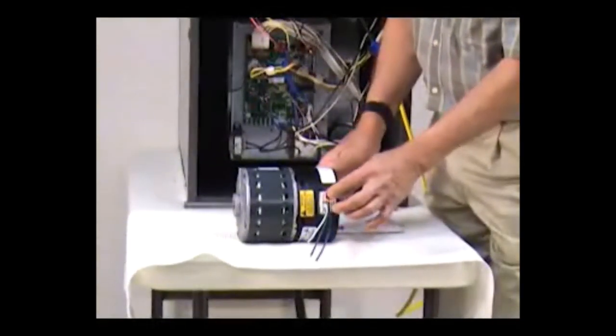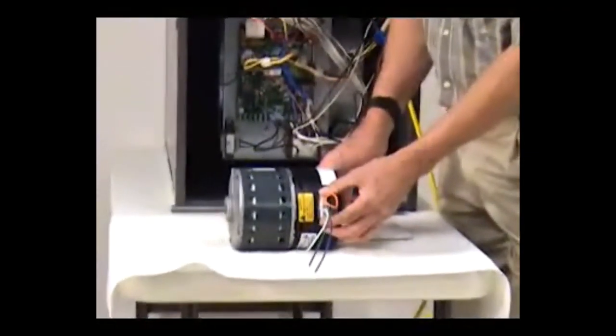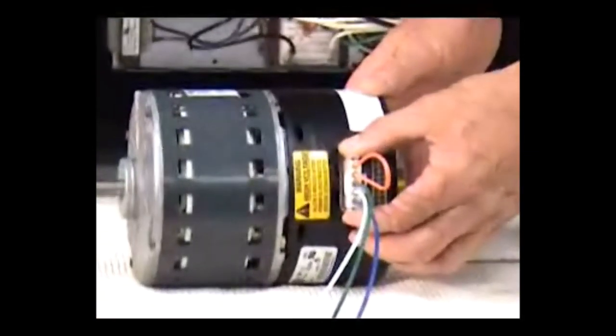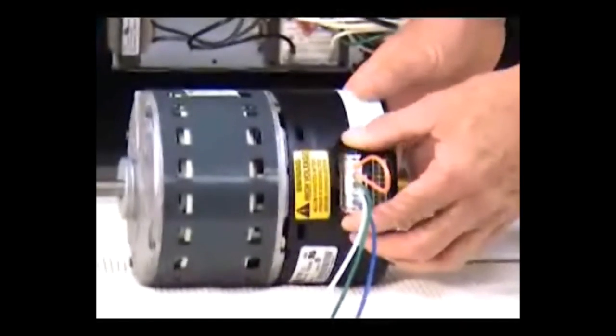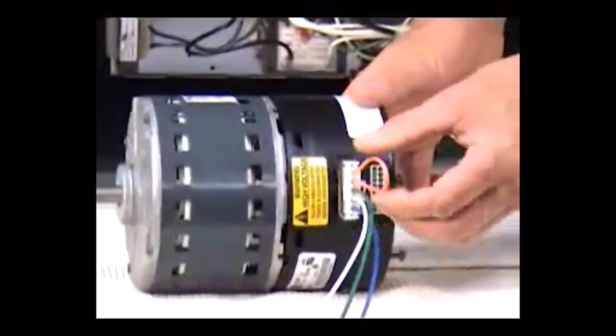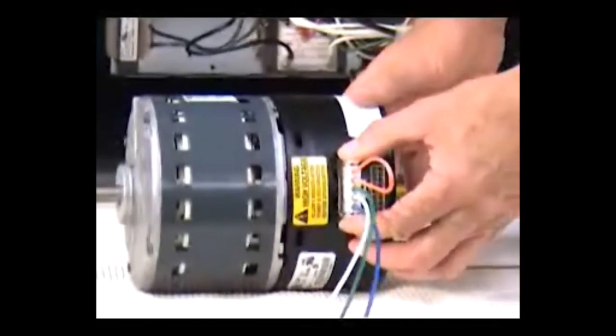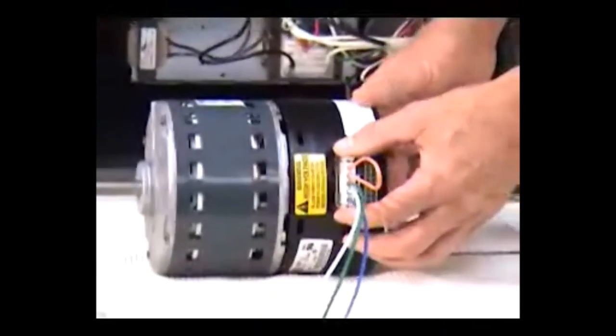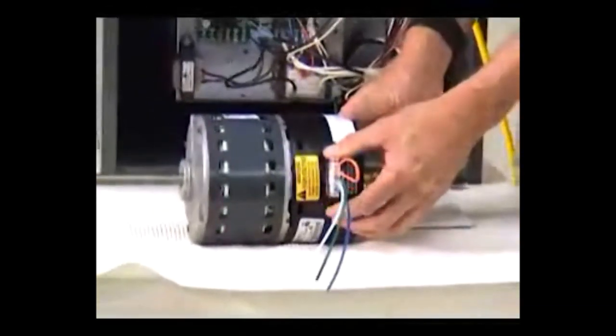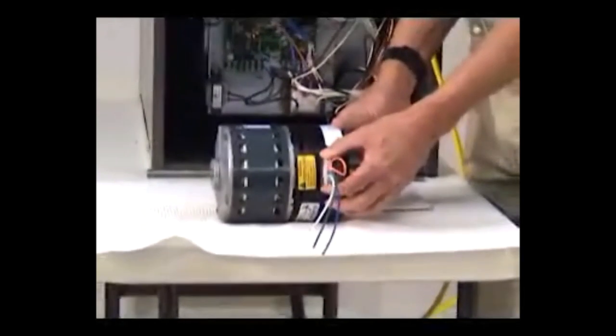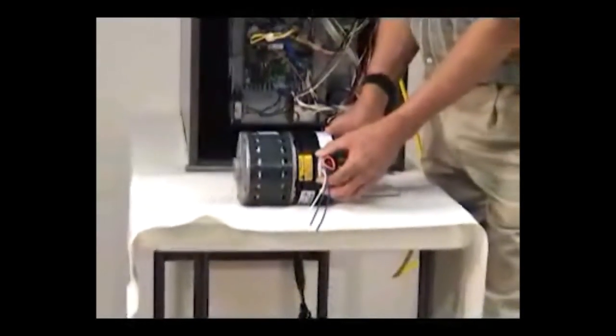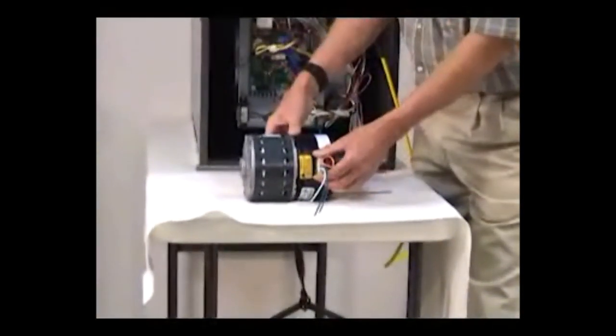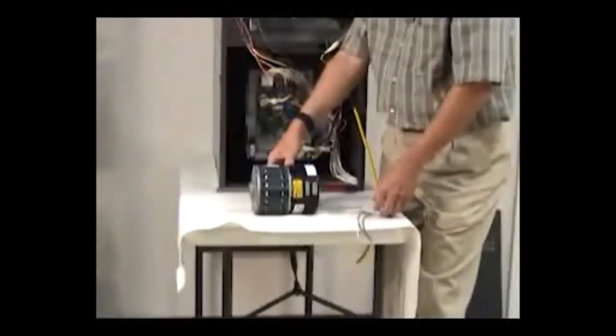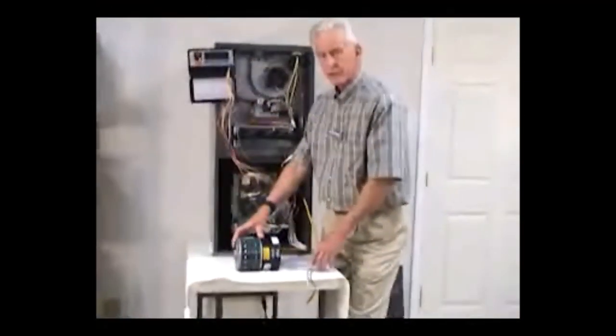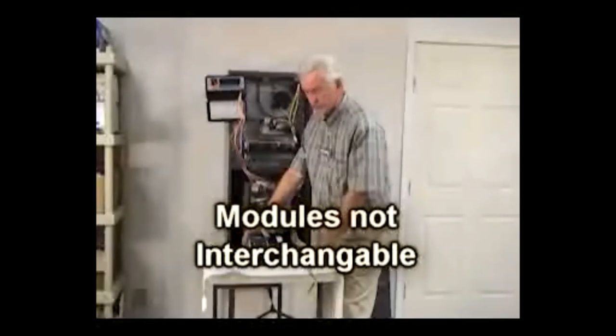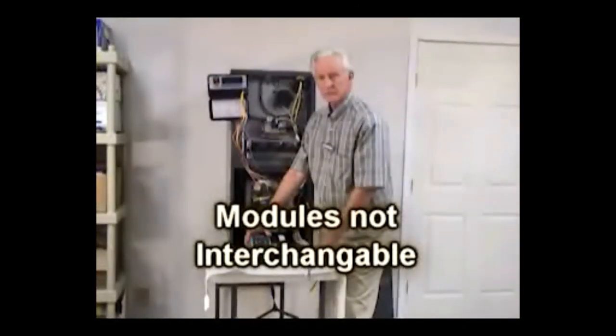If you see a jumper on it like this, that's actually going to be set up for 120 volts. The other arrangement without the jumper on here is going to be for 240 volts. The ranges for 120 volts could be as low as 102 volts through 138 volts. The range for 240 volts could be as low as 204 volts and as high as 276 volts.